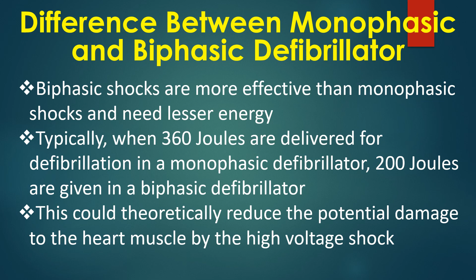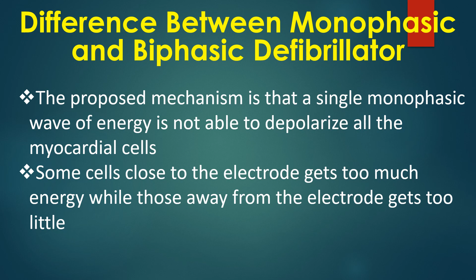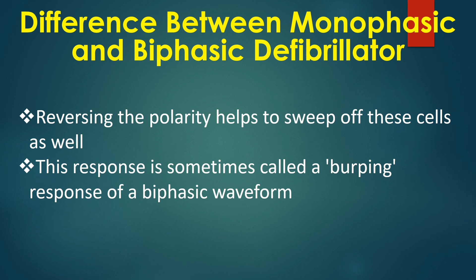This could theoretically reduce the potential damage to the heart muscle by the high voltage shock. The proposed mechanism is that a single monophasic wave of energy is not able to depolarize all the myocardial cells. Some cells close to the electrode get too much energy while those away from the electrode get too little. Reversing the polarity helps to sweep off these cells as well. This response is sometimes called a burping response of a biphasic waveform.